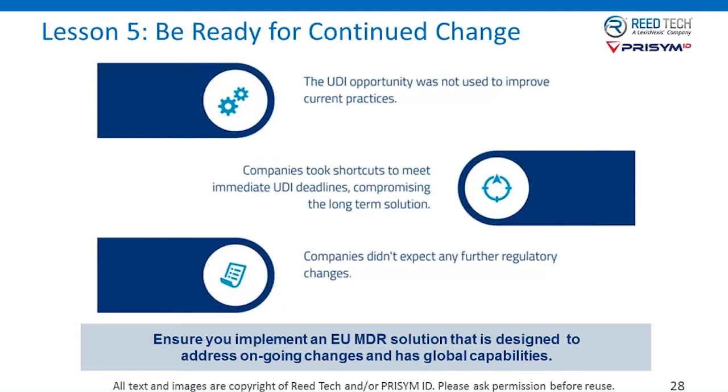The FDA is currently in the middle of a quality improvement for Class 3 and Class 2 devices records that are in place, and we'll have some guidances that will cause some updates. So it's very important to have change management for corrections of the values, to handle new versions and models, and also new products.